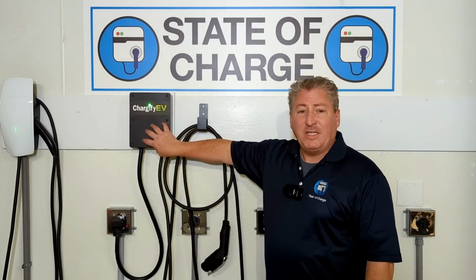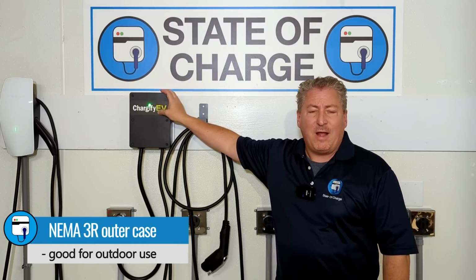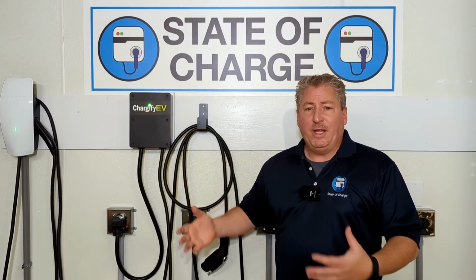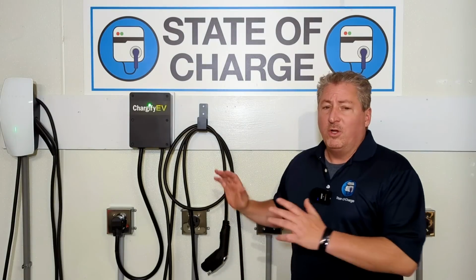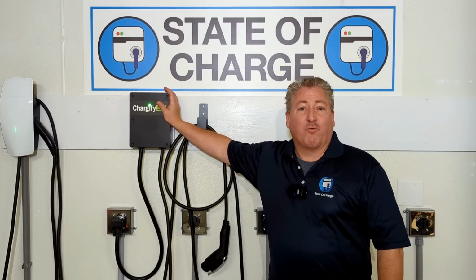Additionally, the casing is NEMA 3R rated, which isn't the best for outdoor weatherproofing, but it's fine and it's okay for outdoor use. So if you did want to install this outside in an area that gets inclement weather, you'd be fine doing so. So that's it for the basic review.